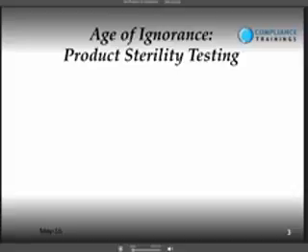Well, let's consider some basic sampling statistics. This table defines the typical operating characteristic curve showing the probability of rejection based on the sample size and the percent of the lot that's contaminated. If, for instance, the lot is X% contaminated across the top, and you take N samples down the left over here, then the number in between is the probability that you'll catch one. The second line here, that's the criteria for the USP sterility test, where a sample size equals 20 and you accept on 0.